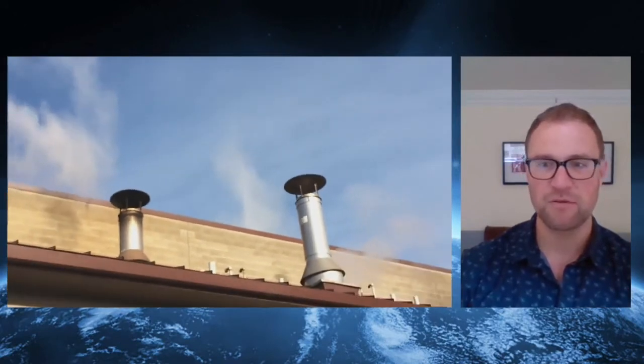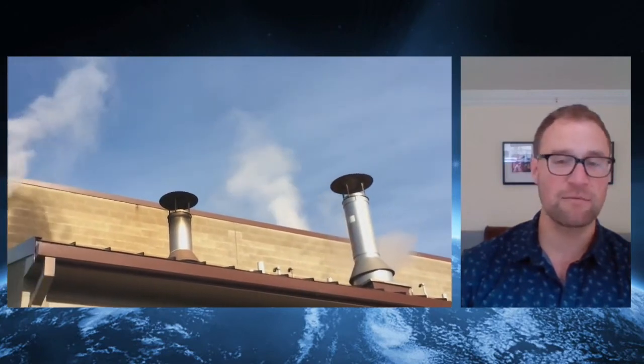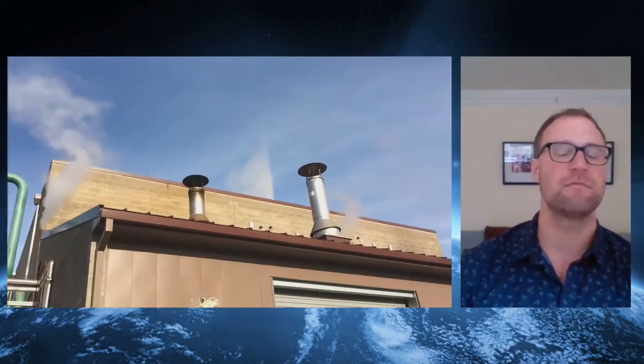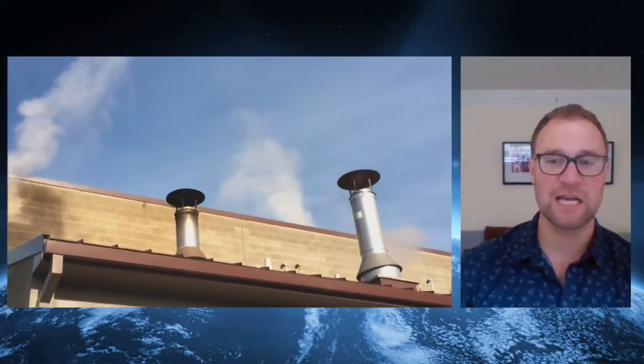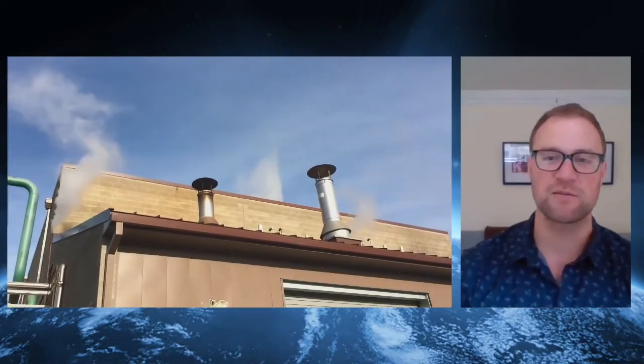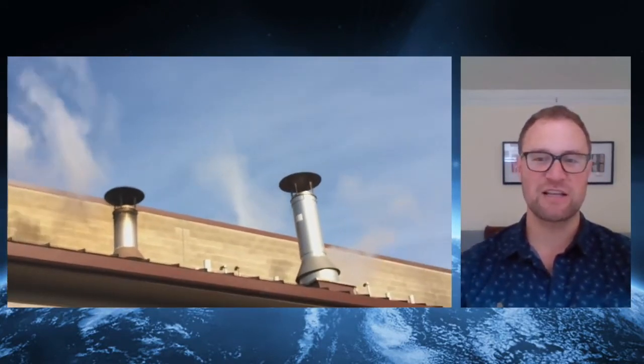What's going on? What that is, is condensate being blasted out of the deaerator tank relief pipe, which is designed to allow a small amount of steam to escape before it's returned to the boiler. And either the wrong trap was installed or it was installed improperly, such that it failed open and a massive amount of steam was leaking by the trap, blowing it out of the DA tank. And keep in mind, this is after the contractor and the customer said, yep, we're all done, come take a look so we can close this and get our incentive check. In this case, this is an energy conservation project that likely had increased energy consumption relative to the baseline before we noticed this problem during M&V.